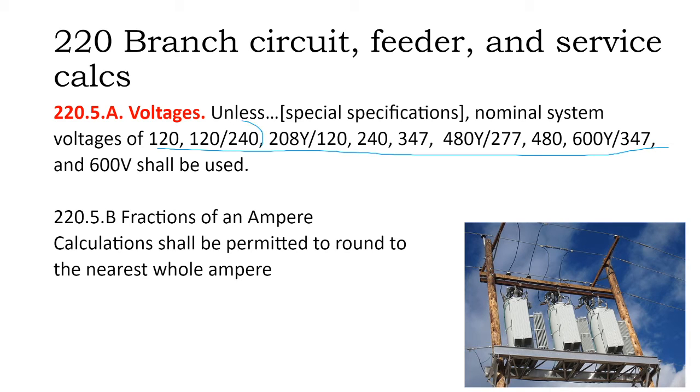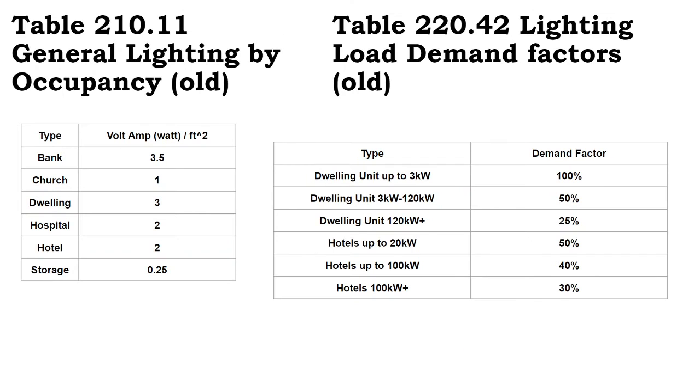On 120/240 residential service out in rural areas, it can easily get up to 125, 126 volts per leg. It varies from utility to utility. It varies with the society's electric load, how much power and the distance of the power. These voltages are just conventional nicknames.